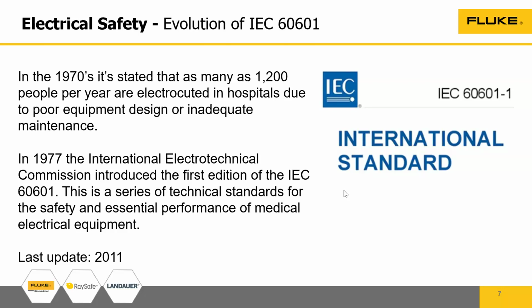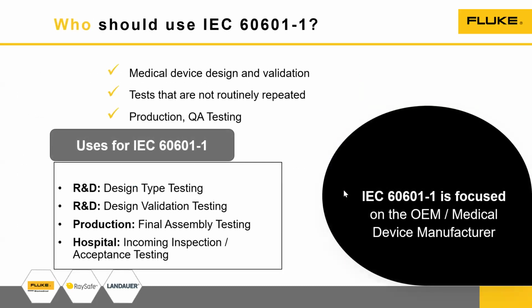For each and every medical device, whether an ECG machine or a CT scan, there are IEC subclauses. IEC 60601-1 has further subclauses based on the medical device. It was last updated in 2011, and another update is expected in a year or so. As I said in the previous slide, it is for medical device design and validation tests that are not routinely repeated. It is mostly for the device manufacturer, R&D, production and production line assembly. Hospitals may or may not use it.